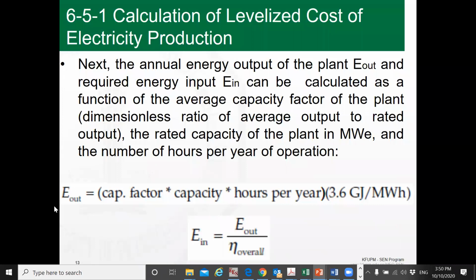So this is how to calculate energy out, as I said: capacity factor, times capacity of the plant in megawatts, times hours of the year, we said 8,000. But this will give us kilowatt hours or megawatt hours, and we need to convert it to joules. So each megawatt hour equals 3.6 gigajoules. I can show you how we get this unit conversion, but it is simple. 1 kilowatt hour means 1 kilojoule per second multiplied by 3,600 seconds, in kilojoules. It will be 3.6 megajoules per kilowatt hour, or 3.6 gigajoules per megawatt hour. So now the energy in is the energy in the fuel. Energy out we calculate from this equation, divided by eta overall, which is eta combustion, times eta thermodynamic, times eta electric generator.